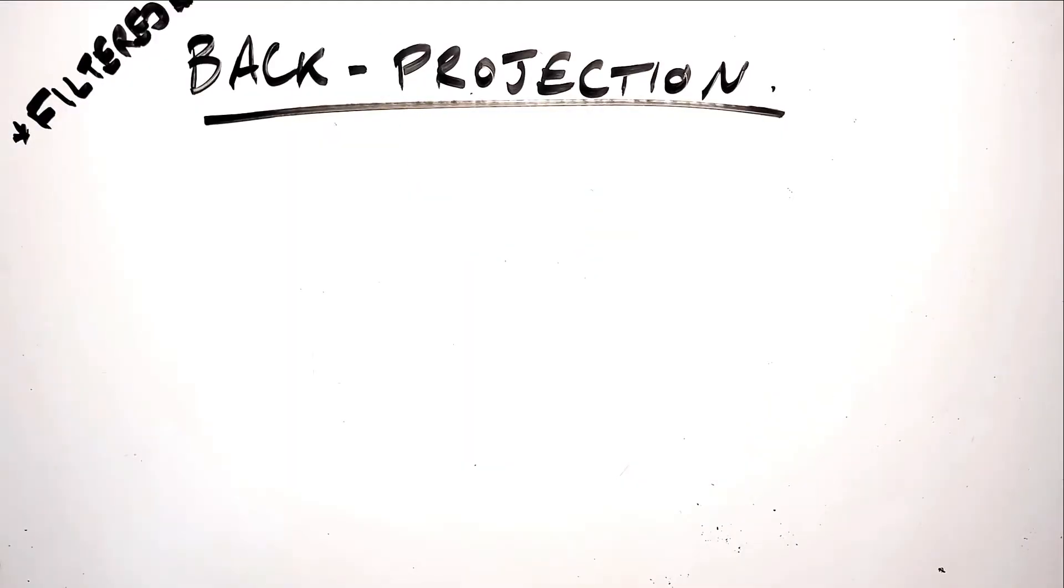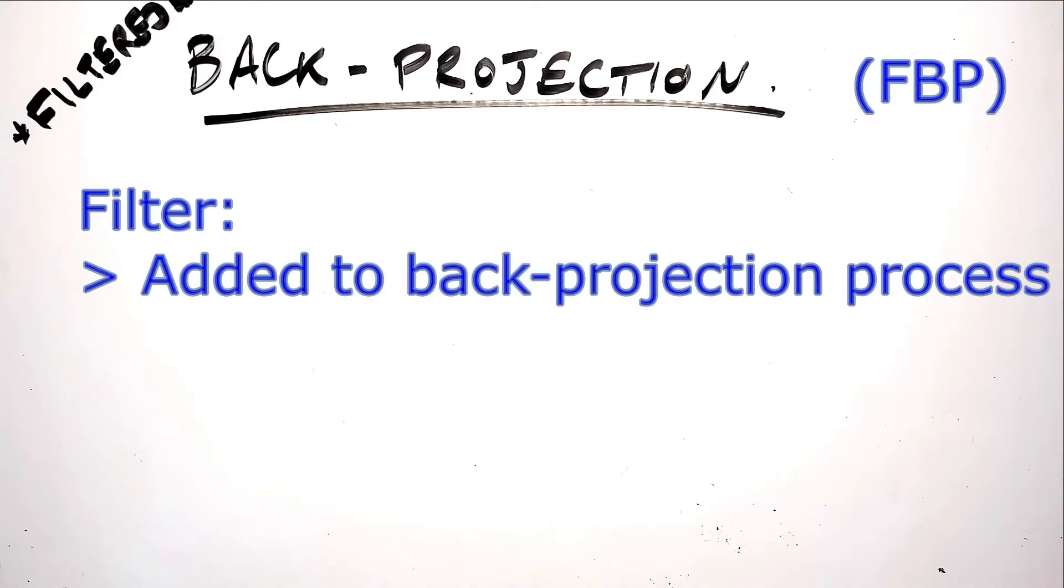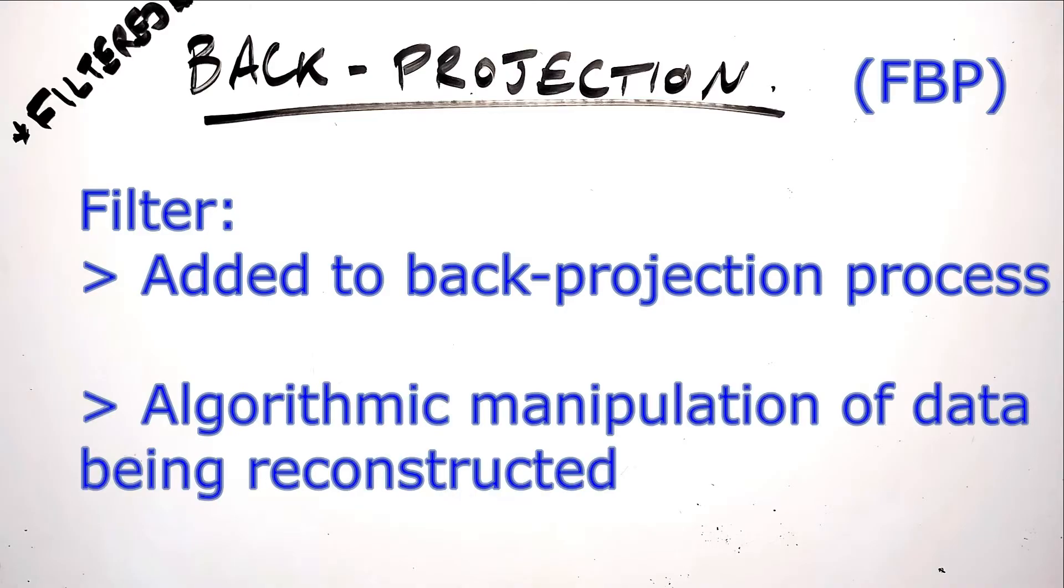The relatively simple process known as back projection is now applied within another process called filtered back projection. All that this means is that a filter is applied to all of the data that's put through the back projection process. A filter, also referred to as a kernel or sometimes just as an algorithm, is a form of data pre-processing and it's an algorithmic manipulation which alters the value of a pixel and its neighboring pixels relative to one another.